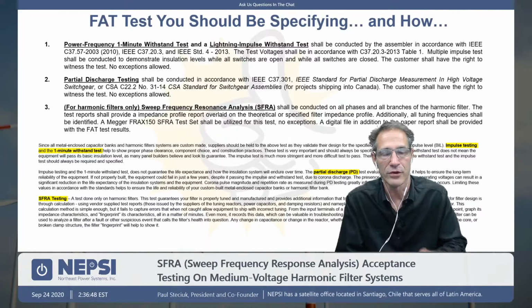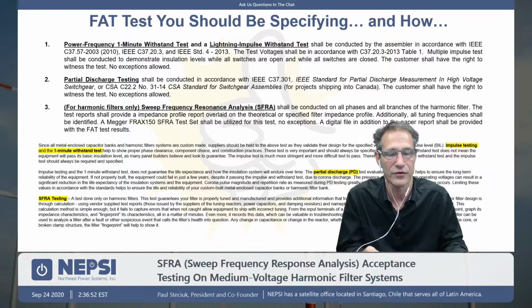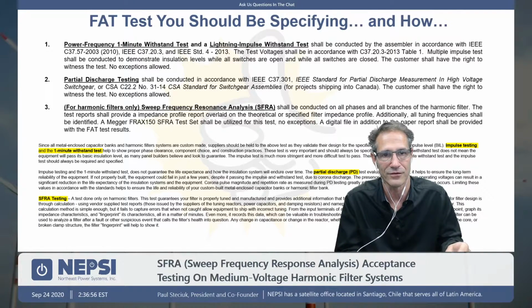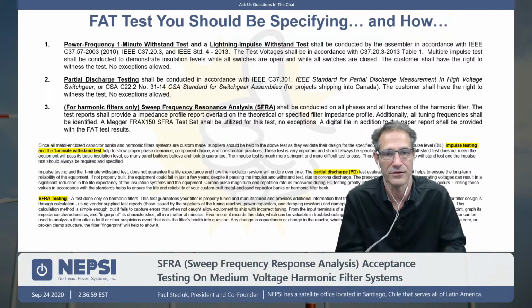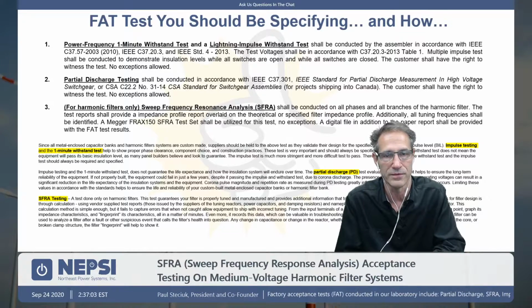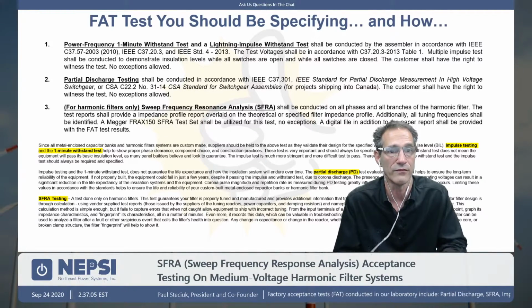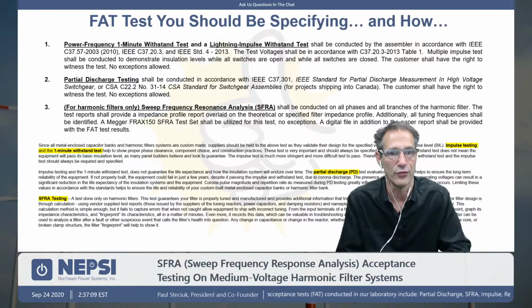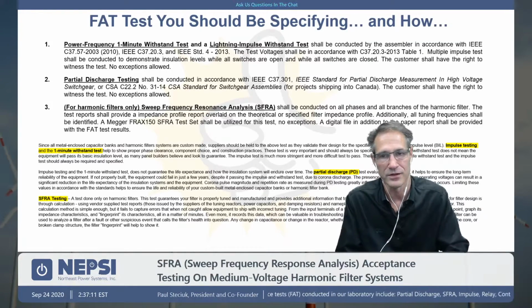So power frequency withstand test, bringing your system up to the power frequency withstand for 1 minute, does not guarantee the phase clearance is met. It just doesn't guarantee it. And we did it that way for years. And we finally did buy this lightning impulse test equipment, and we have learned a lot since then. So if you're specifying an impulse level and you really want to know you're getting it, then ask for the impulse test.